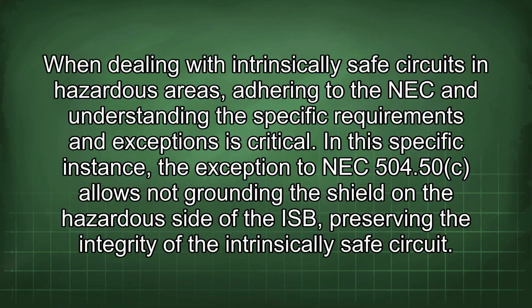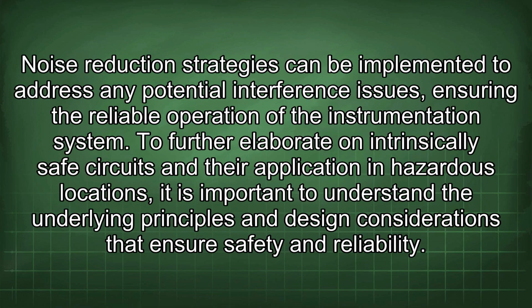When dealing with intrinsically safe circuits in hazardous areas, adhering to the NEC and understanding the specific requirements and exceptions is critical. In this specific instance, the exception to NEC 504.50 allows not grounding the shield on the hazardous side of the ISB, preserving the integrity of the intrinsically safe circuit. Noise reduction strategies can be implemented to address any potential interference issues, ensuring the reliable operation of the instrumentation system.